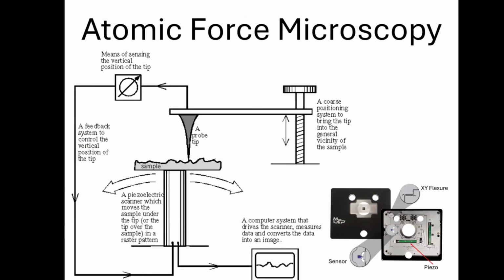Now we're getting somewhere. Here's a full schematic. We can see our probe and sample, our optical beam deflection method, some way to position the tip, a computer for recording the images, some way to move the sample. Here you can see an XYZ piezo tube scanner, and here you can see an XY piezo stack sample scanner. Quite importantly, there's a feedback system. This is at the heart of AFM. It uses the detector signal to make adjustments in the tip sample separation.